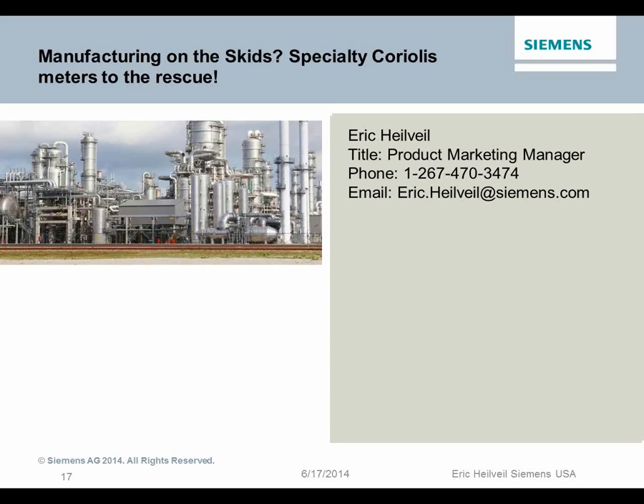So as far as performance goes, it's almost one-to-one. The performance is the same, 1/10% of rate. The variability of the fittings is essentially the same. There are some small differences. Our sensors are a bit smaller, a bit lighter in weight, a very small difference, of course. The immunity to noise really is very dependent on the application, but the Siemens sensor was designed to mitigate that with a series of design changes as well as electronic filtering, and we also considered that when picking the frequencies with which our tubes vibrate.